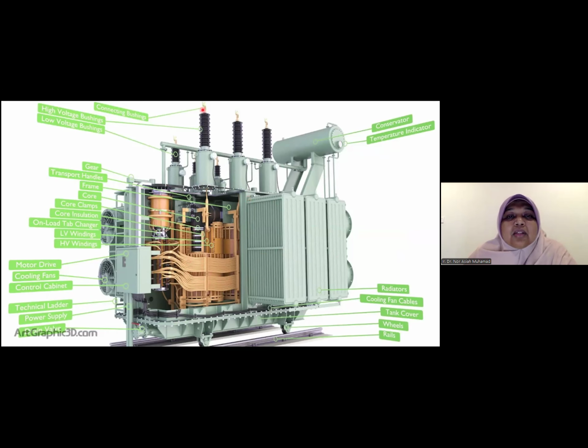The top is the bushing connector. This is where the line from the transmission line is connected into the transformer. The transformer function is to step up or step down. So when it enters from the higher bushing and goes out from the lower bushing, it means it's a step down transformer. This is the high voltage bushing, and this is the low voltage bushing. Most transformers have an automatic gear to adjust for the load, so there is a step changer. There is a motor here, a motorized step changer. And also, lower inside, this is the core, the magnetic core.